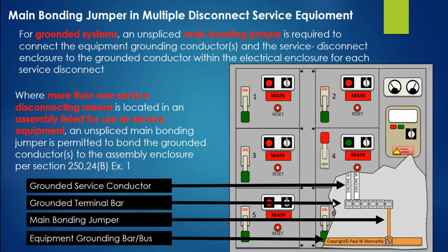Okay, so this is an example of some switchgear, and it states right here in the code: where more than one service disconnecting means is located in an assembly listed for use as service equipment, which is what we have here, an unspliced main bonding jumper is permitted to bond the grounded conductors, these right here, to the assembly enclosure per section 250.24(B) Exception No. 1, which is this allowance to do that. So really the general rule means that I would have to make it in all these locations where there are service disconnects. But this exception allows you to do it in a common location in a listed assembly as service equipment.